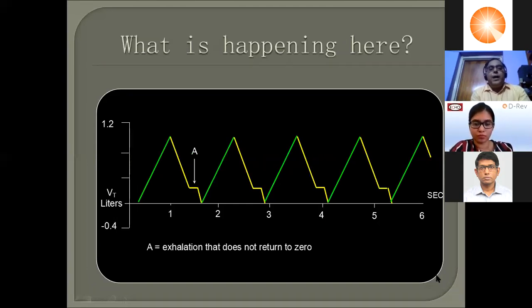This is a volume time scalar. Okay, so your volume is going up, up, up, and then we don't have a plateau phase, and your expiration starts. So maybe it is a sort of volume control without a T pause. But what is important here is you can see the volume is coming down, but never quite reaching the baseline, and then the next one starts. It never quite reaches the baseline. So my expiratory volume does not quite reach there. So what is happening? This is happening because of a leak. So when you have a leak, your volume time scalar does not reach the baseline. So there is a leak somewhere, maybe in the tube, maybe in the circuit. Next one, please.